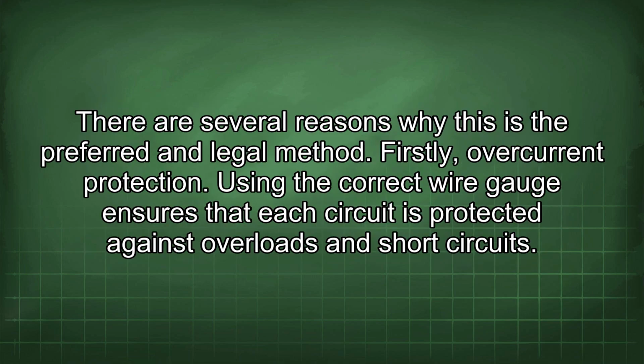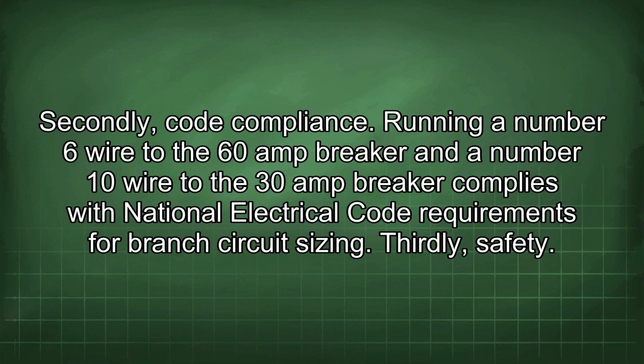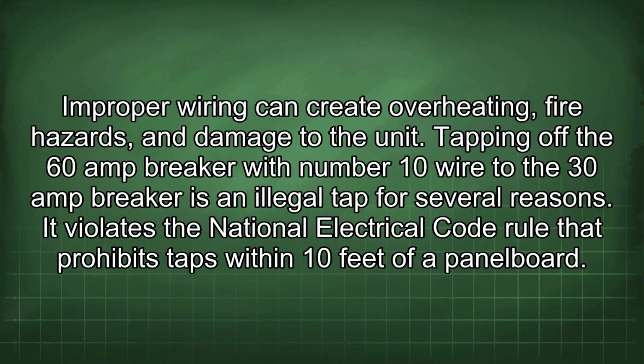There are several reasons why this is the preferred and legal method. Firstly, overcurrent protection. Using the correct wire gauge ensures that each circuit is protected against overloads and short circuits. Secondly, code compliance. Running a number 6 wire to the 60-amp breaker and a number 10 wire to the 30-amp breaker complies with National Electrical Code requirements for branch circuit sizing. Thirdly, safety. Improper wiring can create overheating, fire hazards, and damage to the unit.